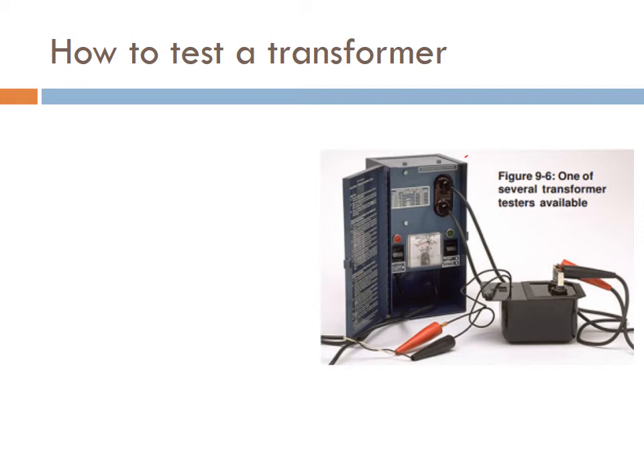If you look here, we have two alligator clips that clip to the transformer, and this will tell you in here how much voltage you're getting out of it. Again, it's always a good idea to keep this running for 10 minutes, because sometimes it will give you 10,000, then it will degrade over time and go down. So this is one way.